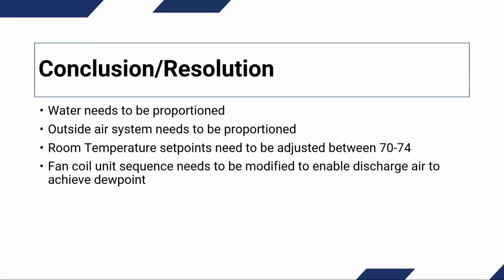So the way this is done is since we have a makeup air unit that's conditioned, the fan coil units ran continuously and the chill water valves cycled open or closed for demand for cooling. So during occupied time, the fan coil unit just ran, getting its conditioned outside air. If there was a call for cooling, the chill water valve would open 100%. We'd reach dew point without a problem. Once demand was met, chill water valve closed.